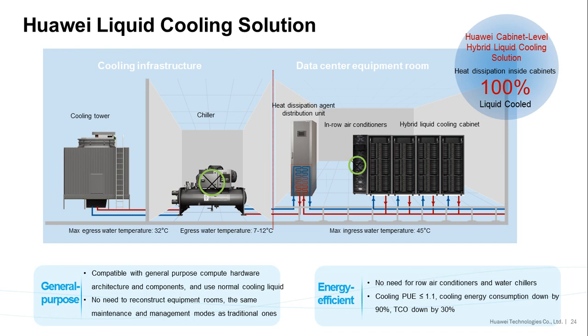Roughly calculated, the liquid cooling solution can reduce power consumption by about 90% and TCO by almost 30%, with a PUE smaller than 1.1. Although liquid cooling involves a larger initial investment than traditional air cooling, according to calculations, the investment can be recovered within 2 to 3 years thanks to the electricity costs saved.